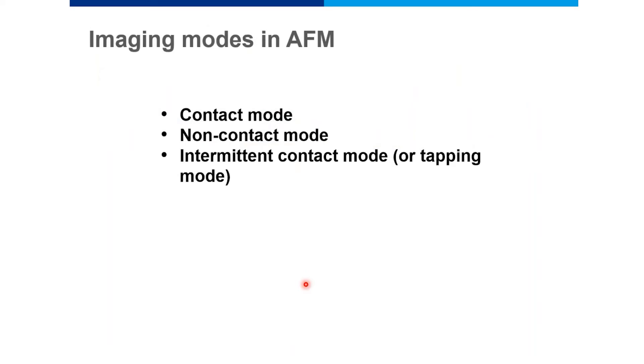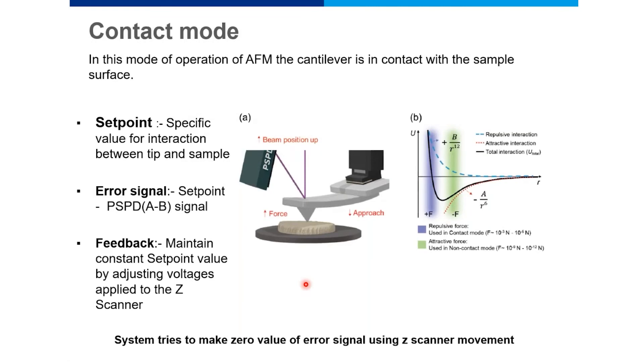Having a basic understanding of the feedback mechanism, let's move to the imaging modes of the AFM. There are three modes: contact mode, non-contact mode, and intermittent contact or tapping mode. In contact mode, the AFM tip or cantilever is in contact with the sample surface — the tip actually touches the sample. In contact mode, we specify the set point for the tip deflection and the laser spot hitting the PSPD, and work to eliminate the error signal using the feedback mechanism.